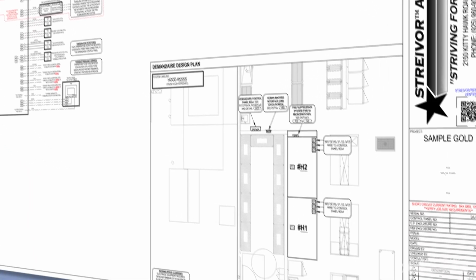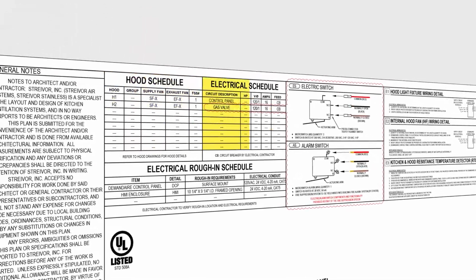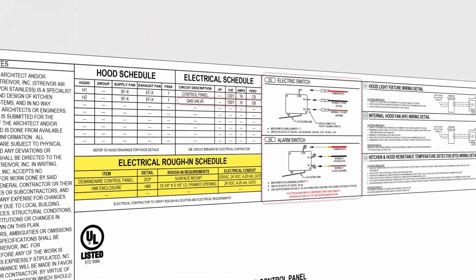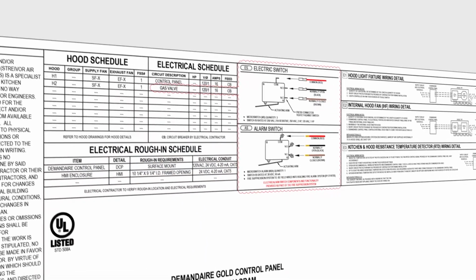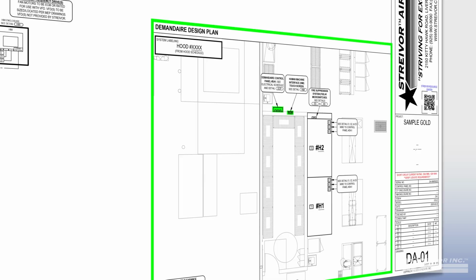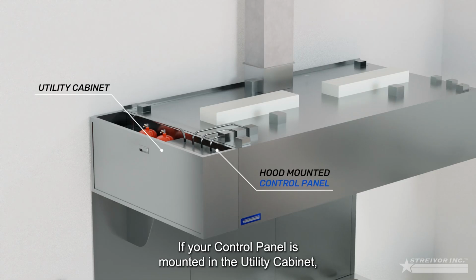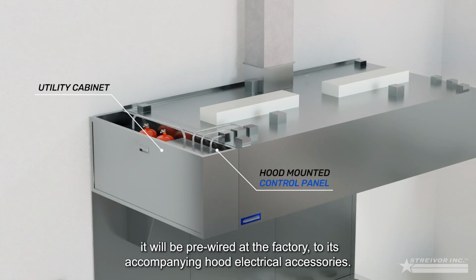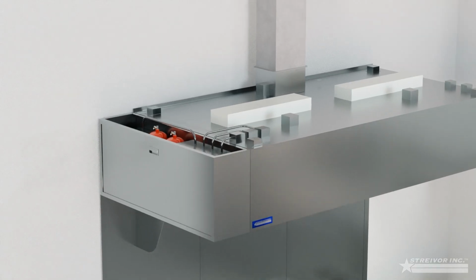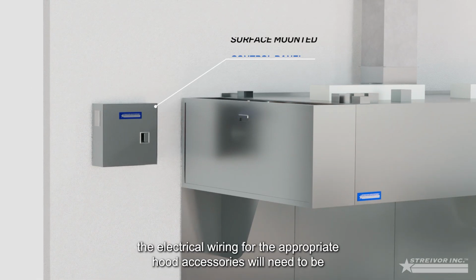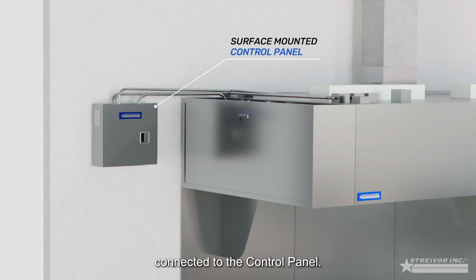Reference the Streivor DemandAire drawing, labeled DA, to obtain installation details from the hood schedule, electrical schedule, and electrical rough-in schedule. Identify the location and mounting method that were specified for the control panel by reviewing the drawing's design plan. If your control panel is mounted in the utility cabinet, it will be pre-wired at the factory to its accompanying hood electrical accessories. For control panels mounted remotely, the electrical wiring for the appropriate hood accessories will need to be connected to the control panel.